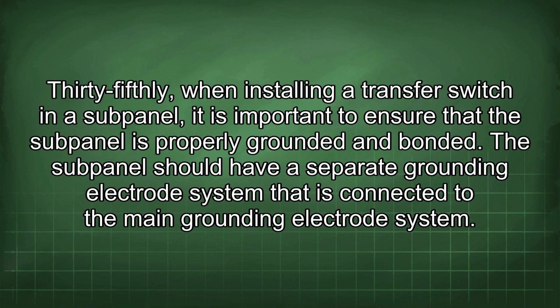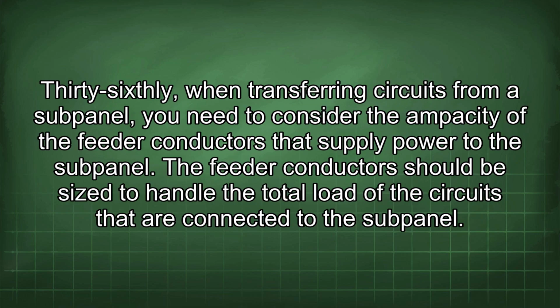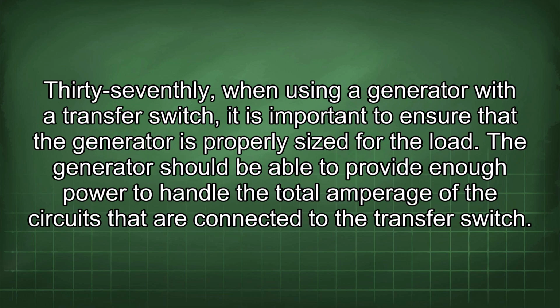36thly, when transferring circuits from a subpanel, you need to consider the ampacity of the feeder conductors that supply power to the subpanel. The feeder conductors should be sized to handle the total load of the circuits that are connected to the subpanel. 37thly, when using a generator with a transfer switch, it is important to ensure that the generator is properly sized for the load. The generator should be able to provide enough power to handle the total amperage of the circuits that are connected to the transfer switch.